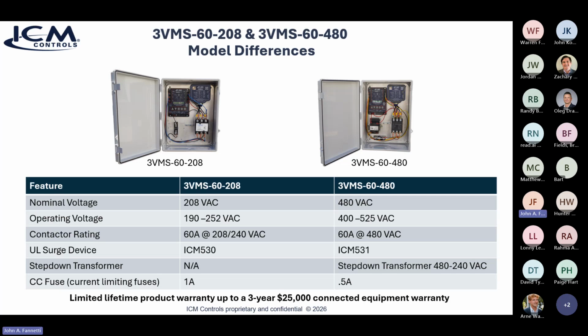Now, if you have a 480 volt application, with three phases at 480 coming in, then you go with the 480 volt model, 3VMS-60-480. That one includes a step down transformer in it to step down the voltage to run the coil of the contactor. Because remember, the 450A, its rating on its little relay that switches the contactor coil on and off is only rated for 240. So we have to step that voltage down. That's why that transformer is in there. Otherwise, we wouldn't need it. Unfortunately, the 450A can't handle more than 240 volts at its output relay to turn off that main relay. Also, it comes with a limited lifetime warranty up to 3 years and a $25,000 connected equipment warranty.